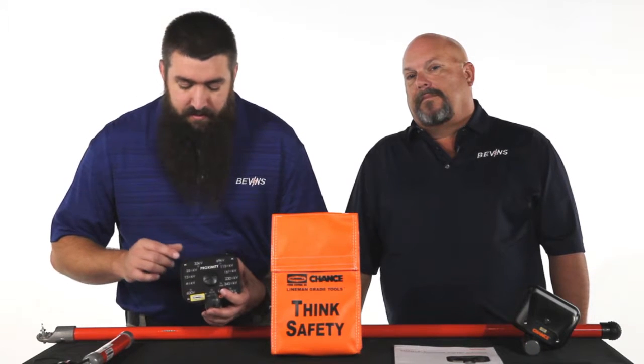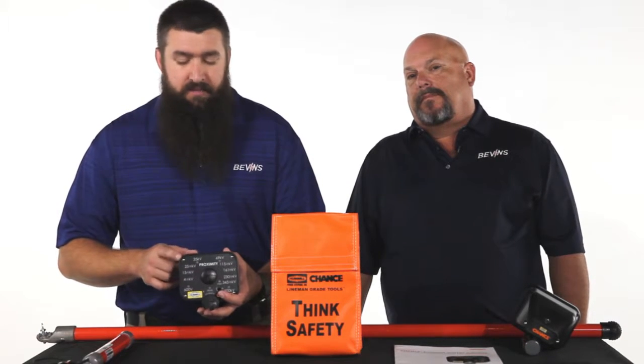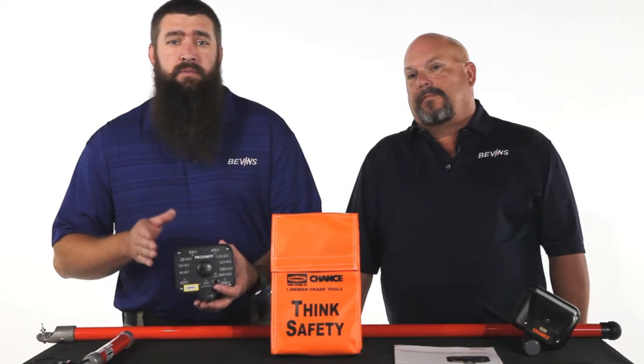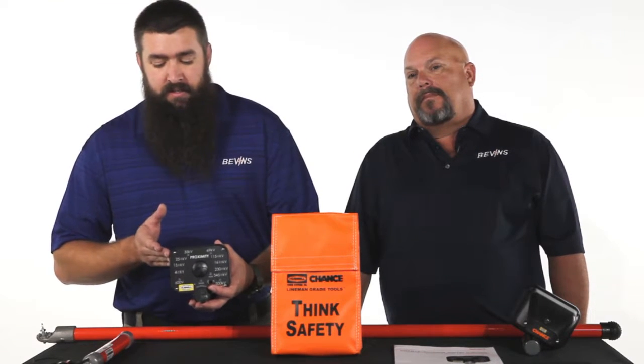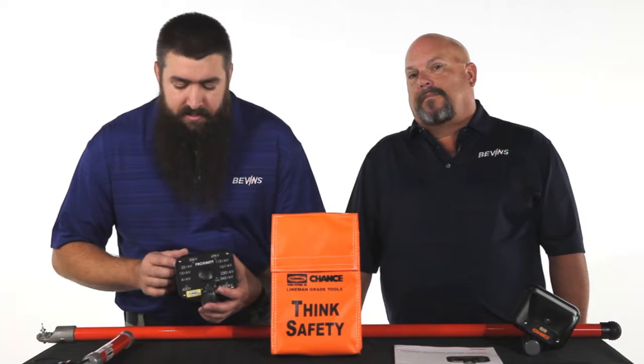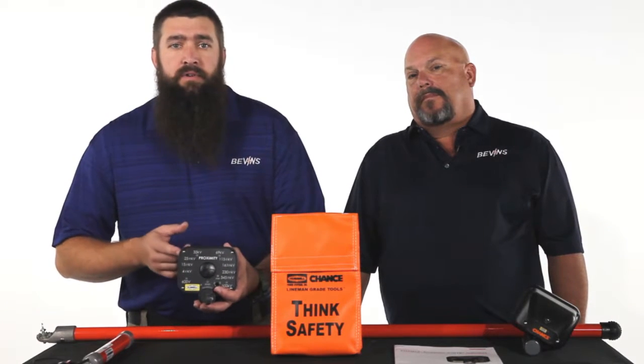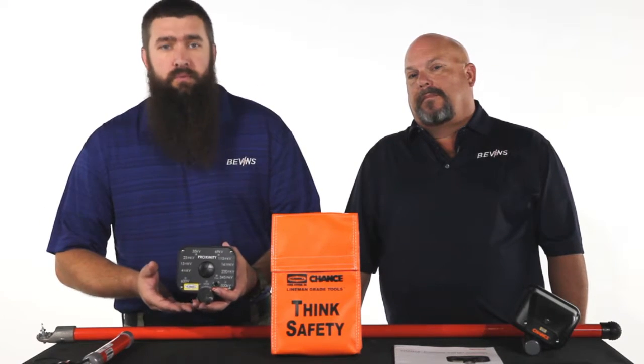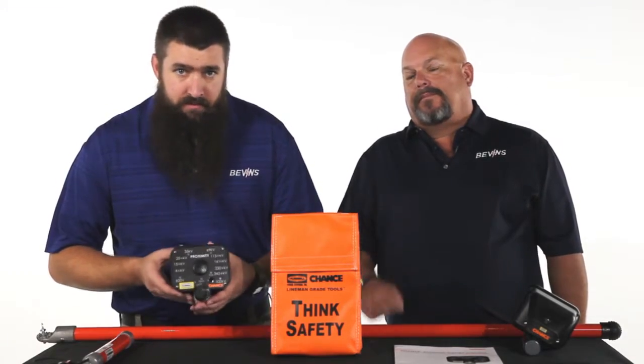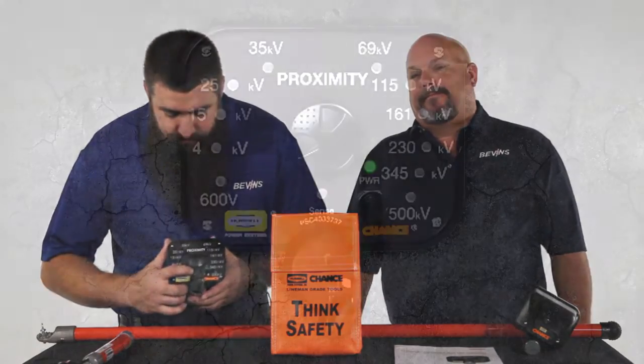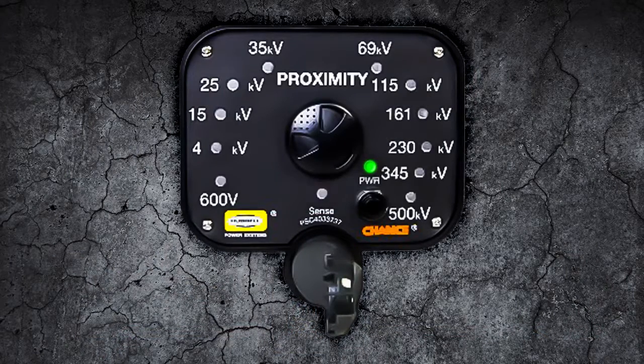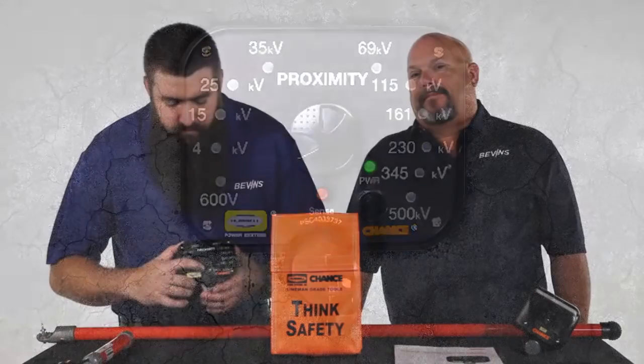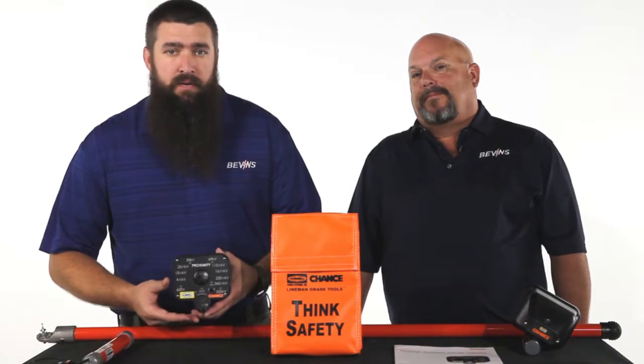And once the target range is achieved, basically this allows the user to disable the audible alarm and the LED ranges below that level. So for example, if we stopped at 25 kV, then everything 25 kV and below will be disabled, with the exception of our sense light. So the sense light here in the middle is flashing all the time the unit's powered on, whether in this advanced mode or not. And when the sense light does indicate voltage, it goes solid. So we did not want to completely disable everything at the lower end.